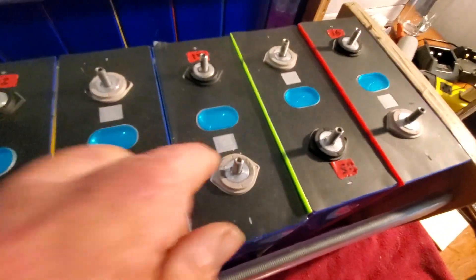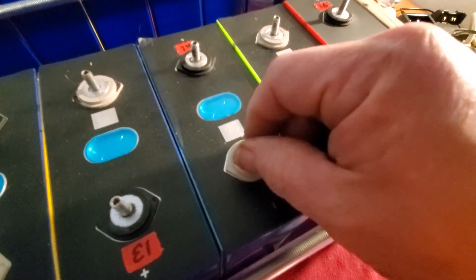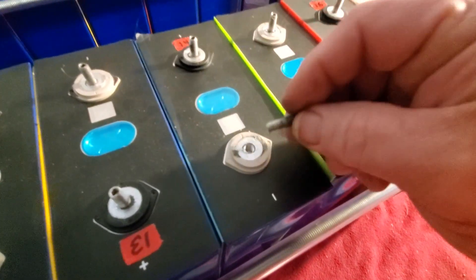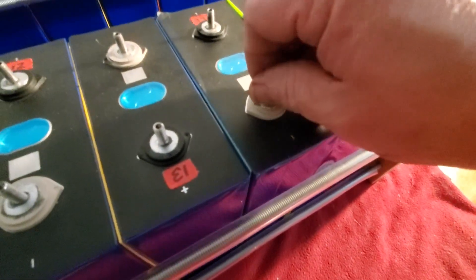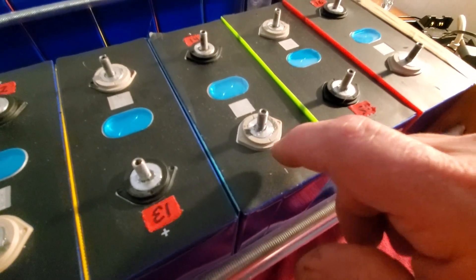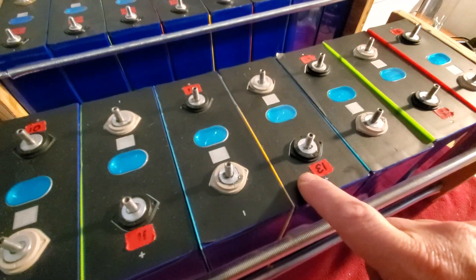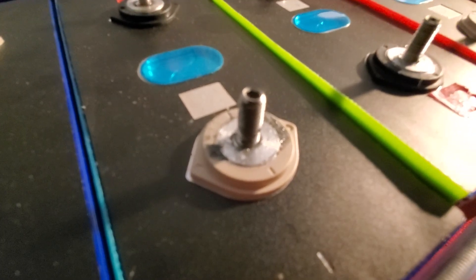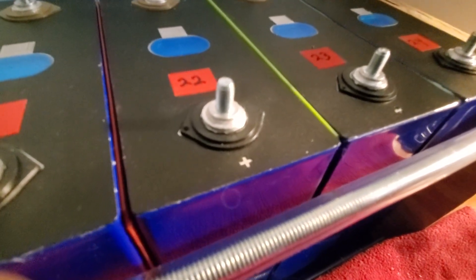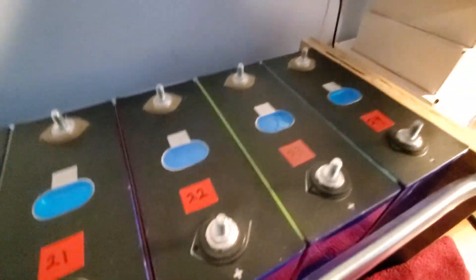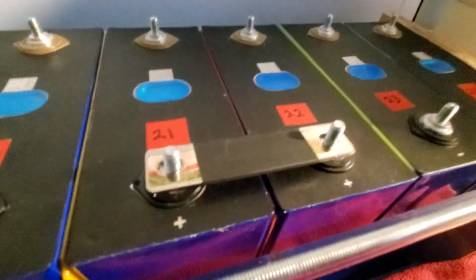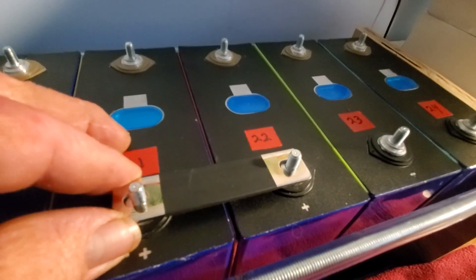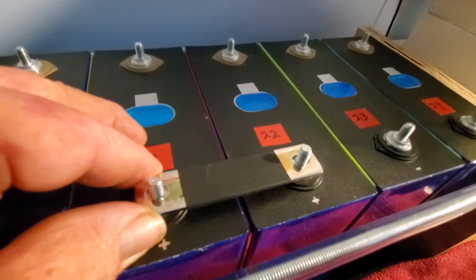These are old school batteries. They got the old studs that screw in, which man you can strip those easy too. And you got to hold it with an allen wrench as you tighten it so it doesn't move or go in there and strip even more. These are a little bit trickier to connect but they have a nice flat base there compared to the studded which you just don't have the surface area. But they seem to work fine. When I do screw these in I usually go this way, this way, and find a happy medium and tighten them like that.